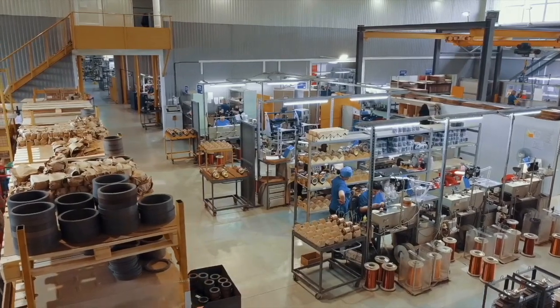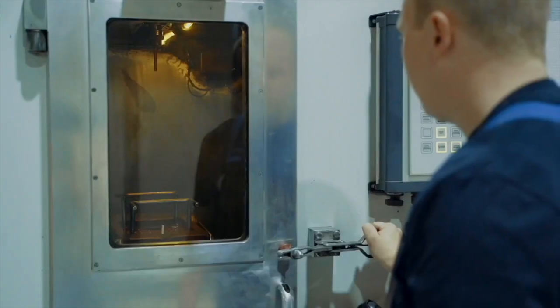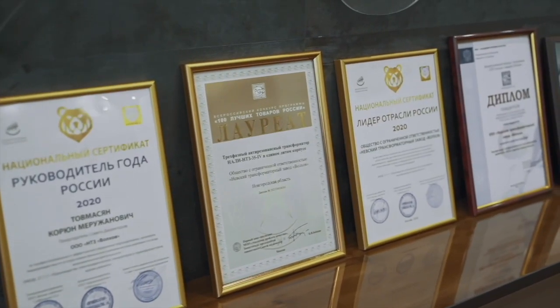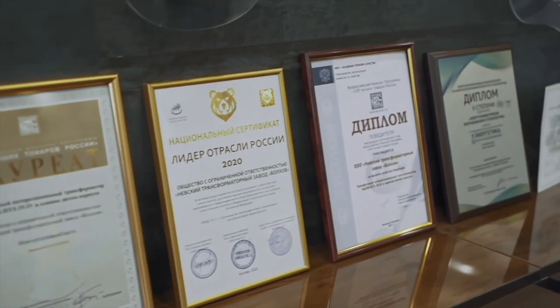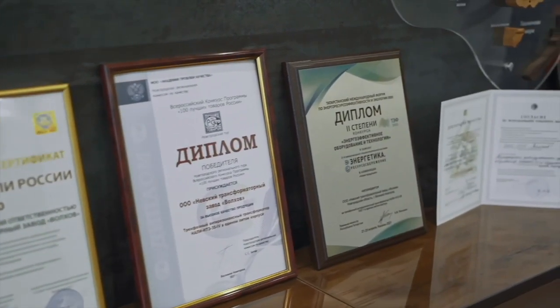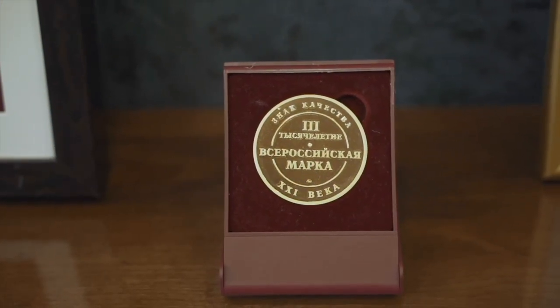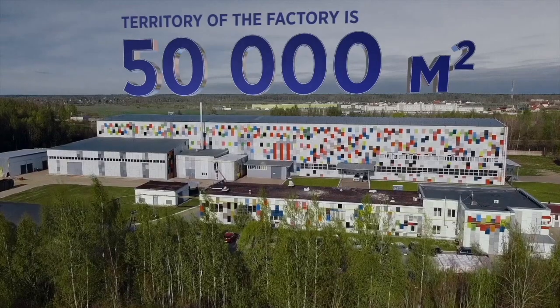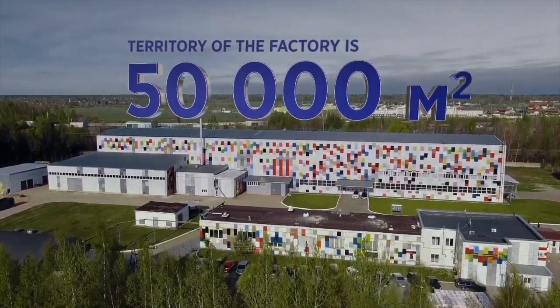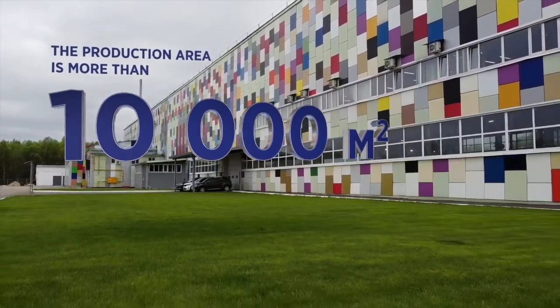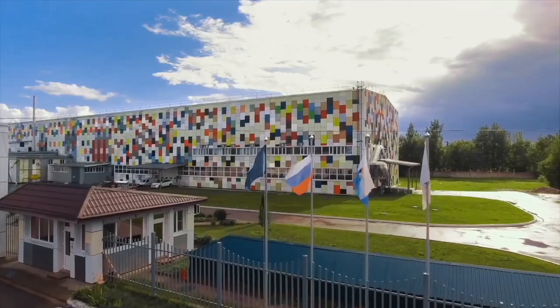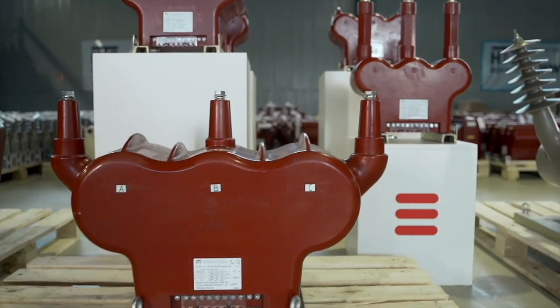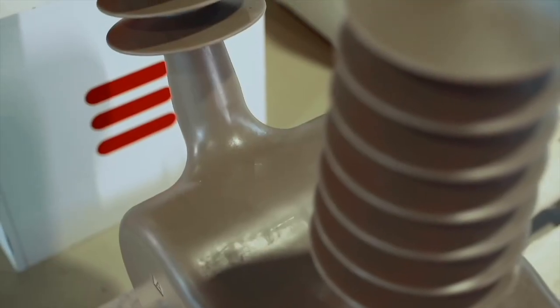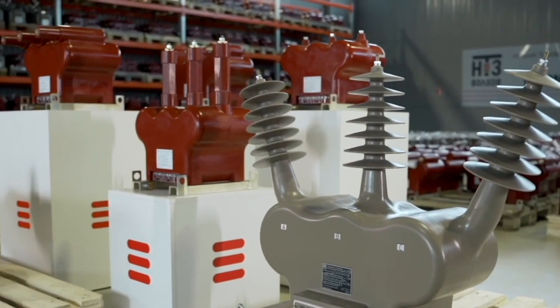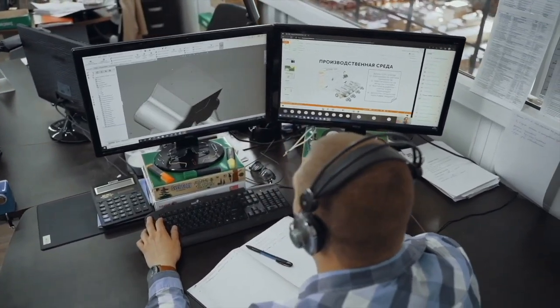This transformer was tested for such impacts as resistance to single-phase phase-to-earth fault, not-full-phase network operation modes, when the transformer is affected by a voltage equal to 4 times U nominal, and other possible impacts without duration limitation. NALI-NTZ transformers are manufactured for all voltage classes from 6 to 35 kV. Anti-resonance instrument voltage transformers NALI-NTZ have no analogs. These are new generation voltage transformers that will inevitably replace old solutions. We are sure that the future belongs to them.